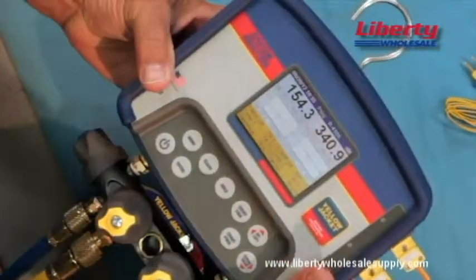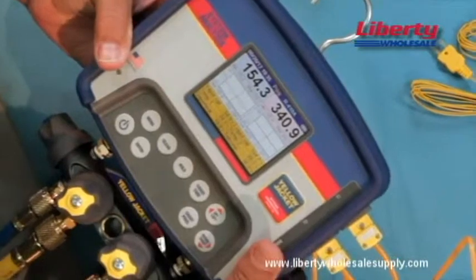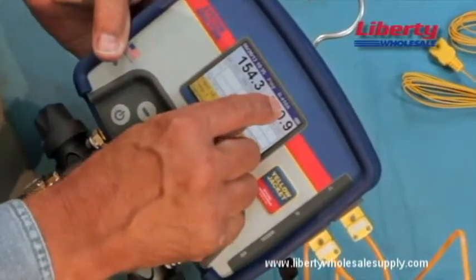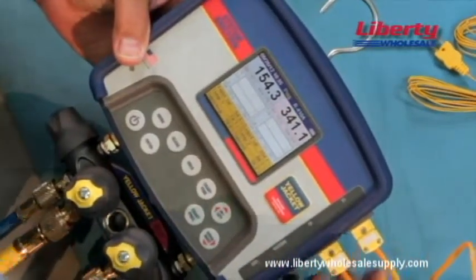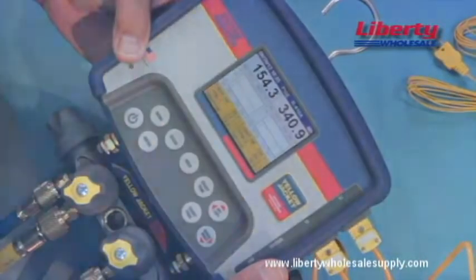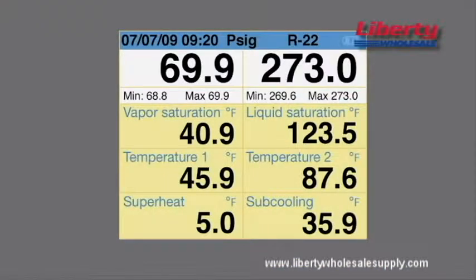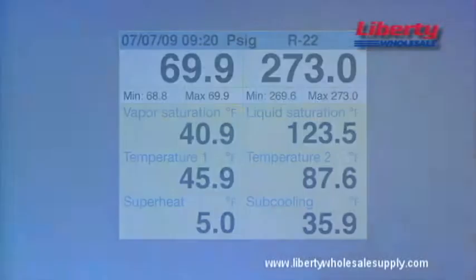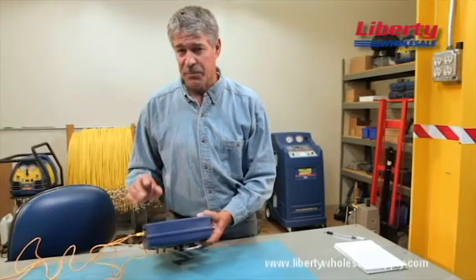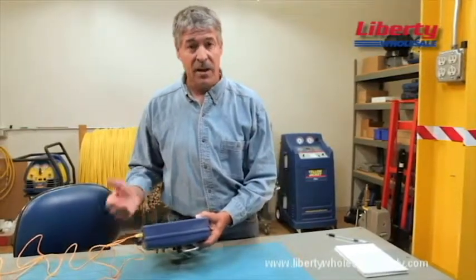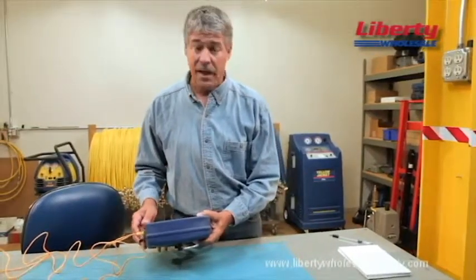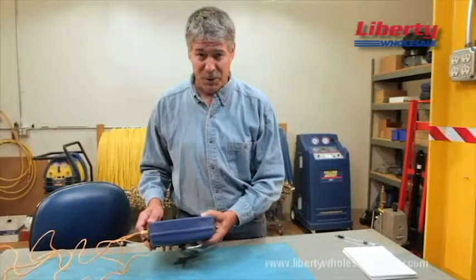If you're using a refrigeration system analyzer, simply select the appropriate refrigerant and connect the hoses and thermocouples to the system for an immediate reading. The unit will automatically determine saturation temperatures and calculate the superheat and subcooling. For the most precise readings, make sure your refrigeration system analyzer has elevation compensation settings and accurate temperature probes.